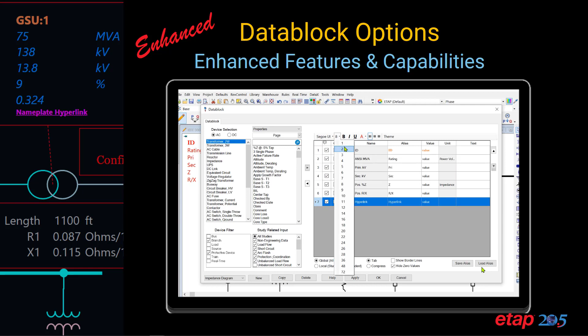If you open up the data block editor and quickly search for hyperlink, you can now insert a hyperlink tag onto the data block. Once you define a hyperlink for a component, it appears directly on the data block. Drag and drop the hyperlink button, type in or browse for the file you'd like to link to, for example an image file. Put in a meaningful description, such as nameplate for this transformer. Click add, and you can click on the link to test it. Once you click OK, you'll see the hyperlink on your data block, where you can change the justification, select the style, and change the font size as needed.